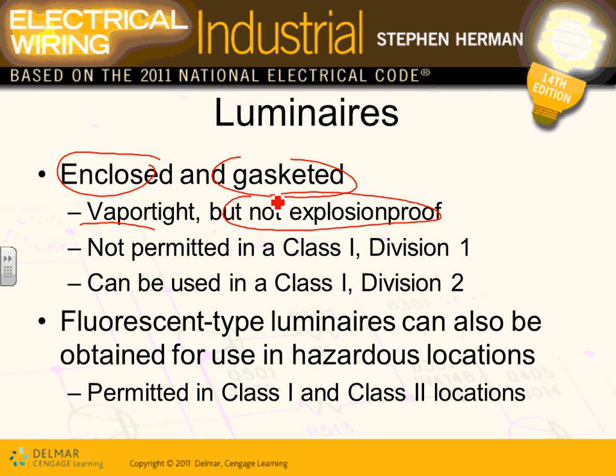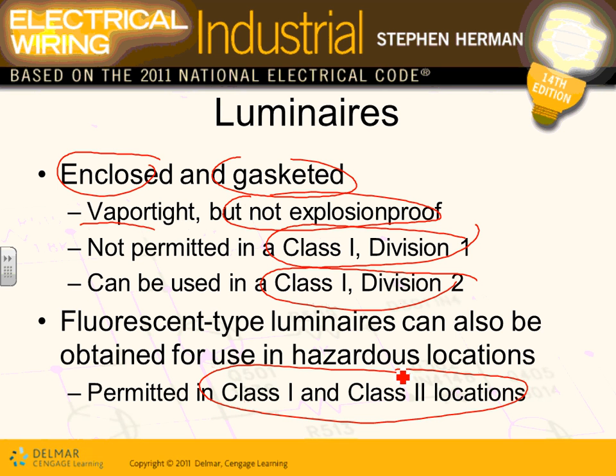These are not permitted in a Class 1 Div 1 because they need to be explosion-proof. They can be used in Class 1 Div 2. So guys, an explosion-proof lighting fixture like this can be used anywhere. But it's expensive. In order to make a cheaper piece of equipment, Derek, they have something called an enclosed and gasketed fixture, which is cheaper. But you can't use it in a Class 1 Div 1. You have to use it only in Class 1 Div 2. So that's cheaper equipment. Fluorescent type luminaires can also be obtained for hazardous locations, permitted in Class 1 and Class 2 locations. So a lot of these guys, they can get incandescent or fluorescent fixtures that you can use as explosion-proof or enclosed and gasketed fixtures.